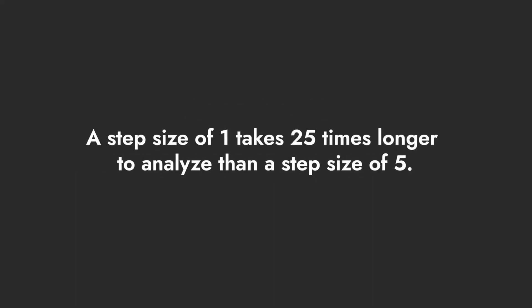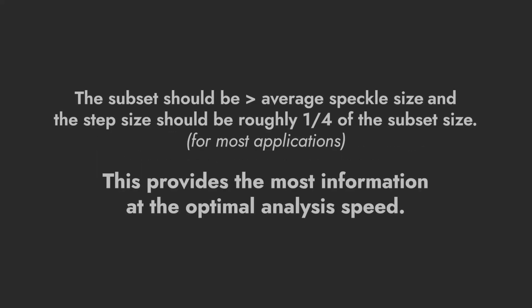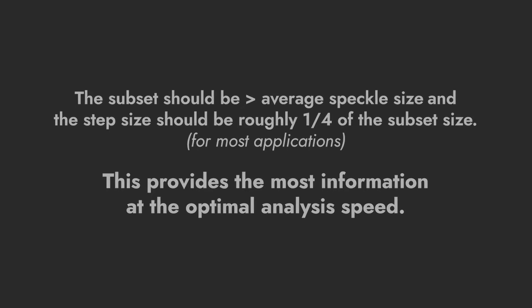Note, analysis time varies inversely with the square of the step size. In other words, a step size of 1 takes 25 times longer to analyze than a step size of 5. In short, the subset should be larger than the average speckle size, and for most applications, the step size should be roughly one-fourth of the subset size. This provides the most information at the optimal analysis speed. For a subset size of 21, we'll set the step size at 5.